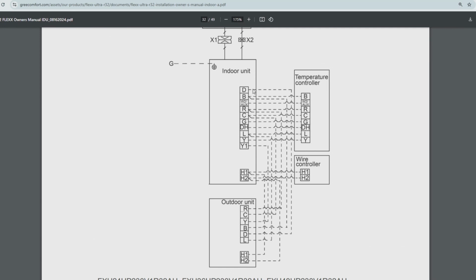If you do have 24 volts applied to the W2 auxiliary terminal from your thermostat, in other words, the heat pump is running in heat pump heating mode and auxiliary heat is running at the same time, the blower will not shut off. It will stay on. So that's the way it works. And again, keep in mind, guys, these things are not in defrost long. About 2 minutes.